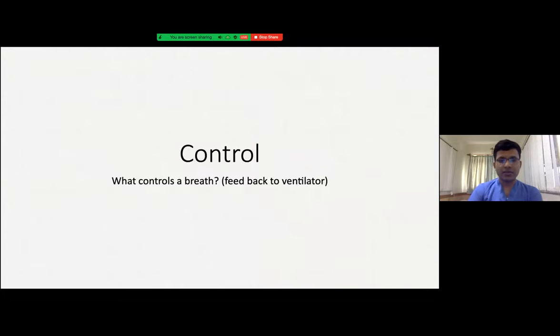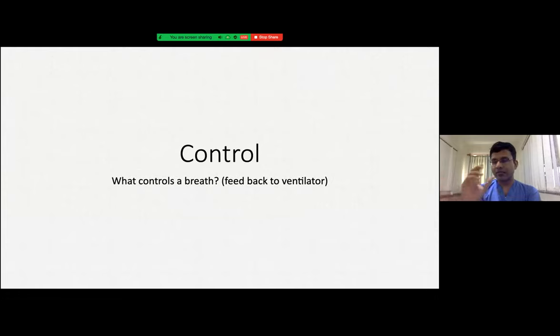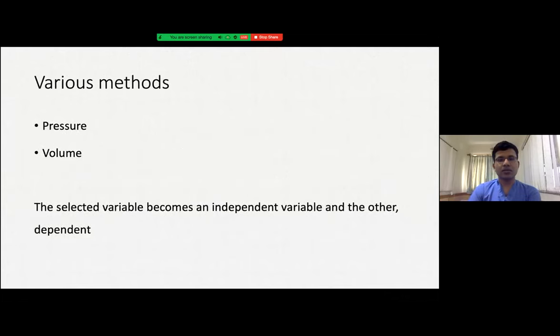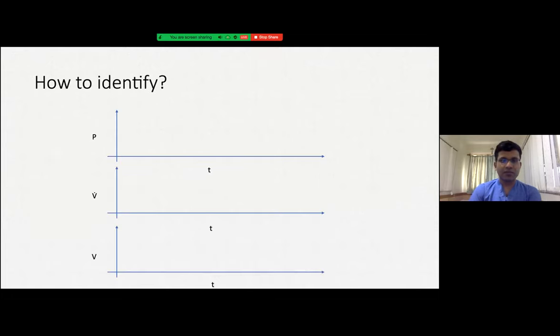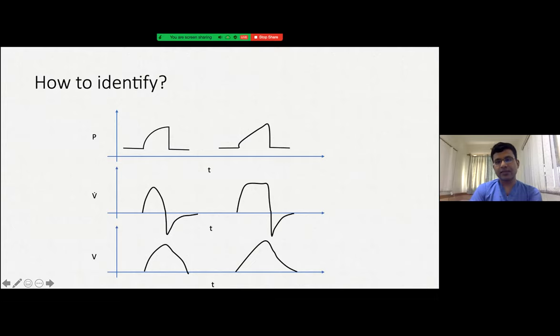Control is what actually controls a breath — usually pressure or volume control, with flow control being rarely used. In pressure control, the ventilator looks only at pressure and regulates the other two parameters based on it. In volume control, it focuses regulation on volume, and flow and pressure are managed accordingly. On the pressure time scalar, only the pressure curve is smooth while flow and volume are titrated accordingly. In volume control mode, the volume curve is smooth while pressure and flow are titrated accordingly.